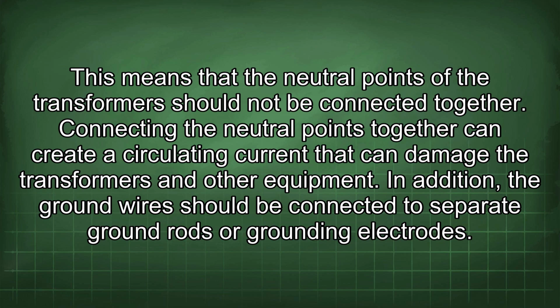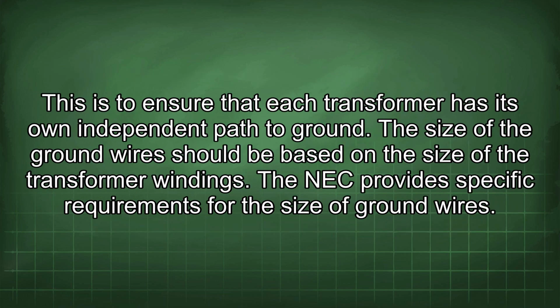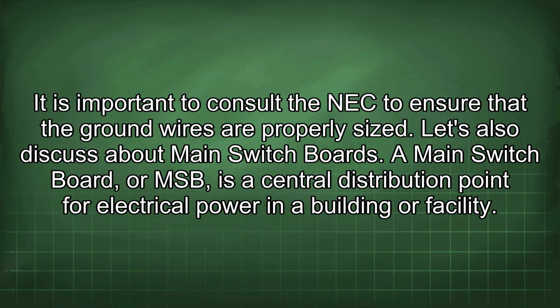In addition, the ground wire should be connected to separate ground rods or grounding electrodes. This is to ensure that each transformer has its own independent path to ground. The size of the ground wire should be based on the size of the transformer windings. The NEC provides specific requirements for the size of ground wires. It is important to consult the NEC to ensure that the ground wires are properly sized.